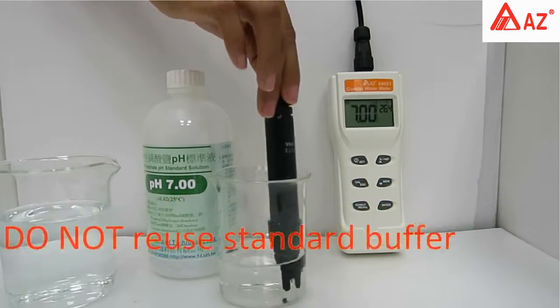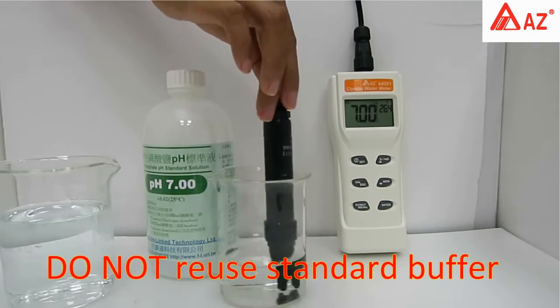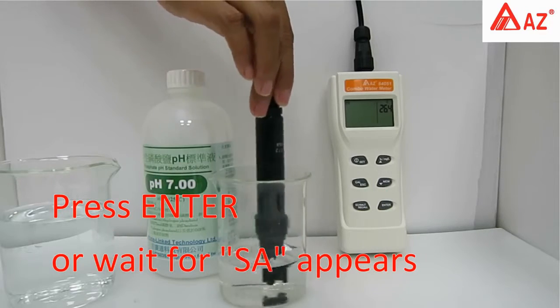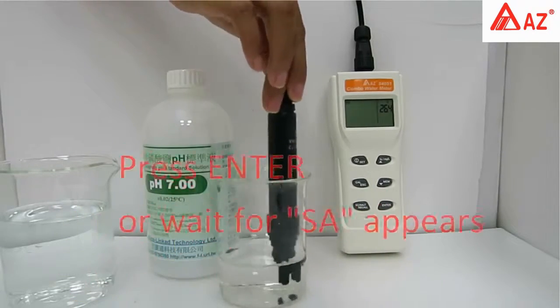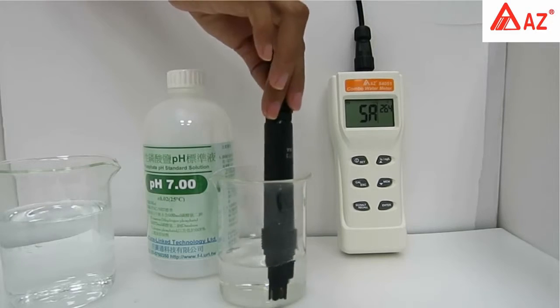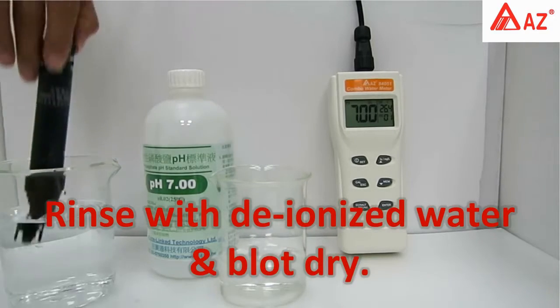Do not reuse standard buffer. Once the reading stabilizes, press enter, or wait for the SA icon to appear when the result is automatically saved. Rinse the probe with deionized water and blot dry.